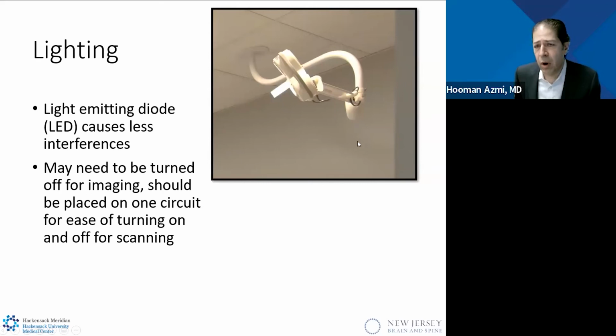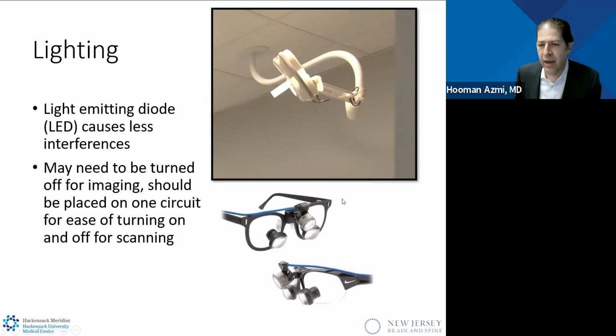Lighting. There are MR compatible lighting systems available. There are LEDs. What we learned was that turning them on and off is a button on them, and it becomes extremely inconvenient. So if anyone's considering doing this, I would suggest putting them on one circuit with one button to turn it on and off at the door. Because it's so inconvenient, we basically stopped using them, and ultimately this is what we use. We have loupes with personal lights on them, and we have not had any trouble, and the illumination has been great.